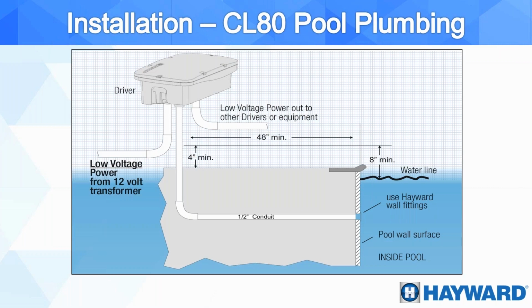And again, if we are going to be using the ColorLogic 80 in the pool, the same recommendations apply. Minimum 48 inches away from the water's edge. Remember, this is half an inch conduit because that light goes inside half an inch pipe. I'm sorry, so half an inch conduit goes back into our driver, and the driver needs to be minimum 48 inches away from the water's edge, and minimum 8 inches above the water line.